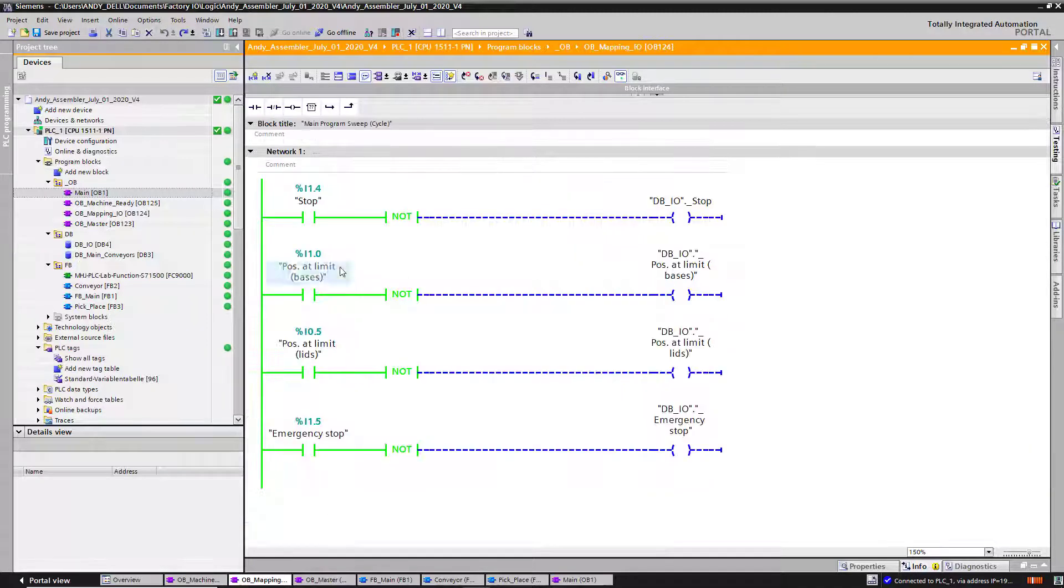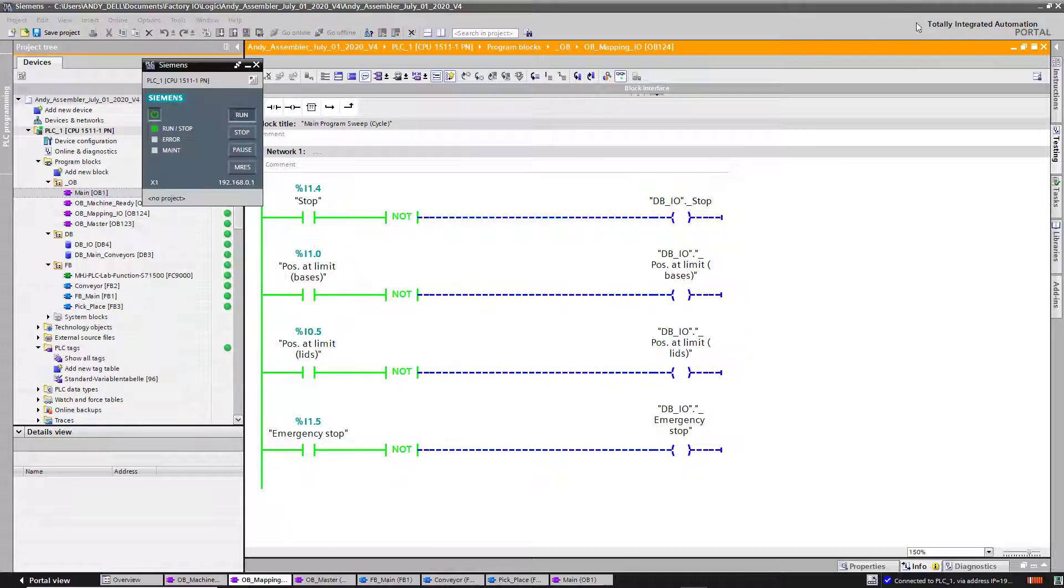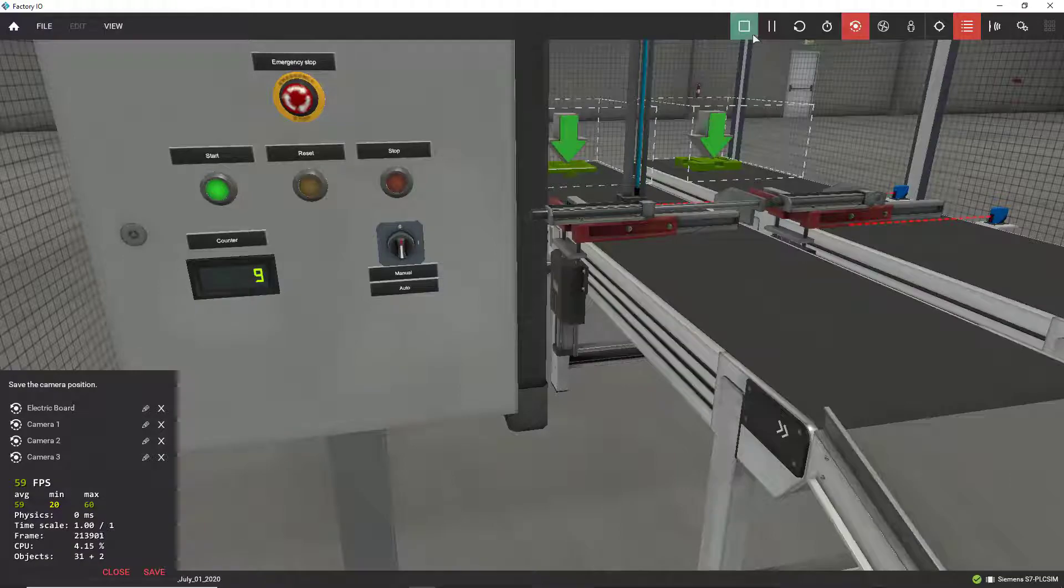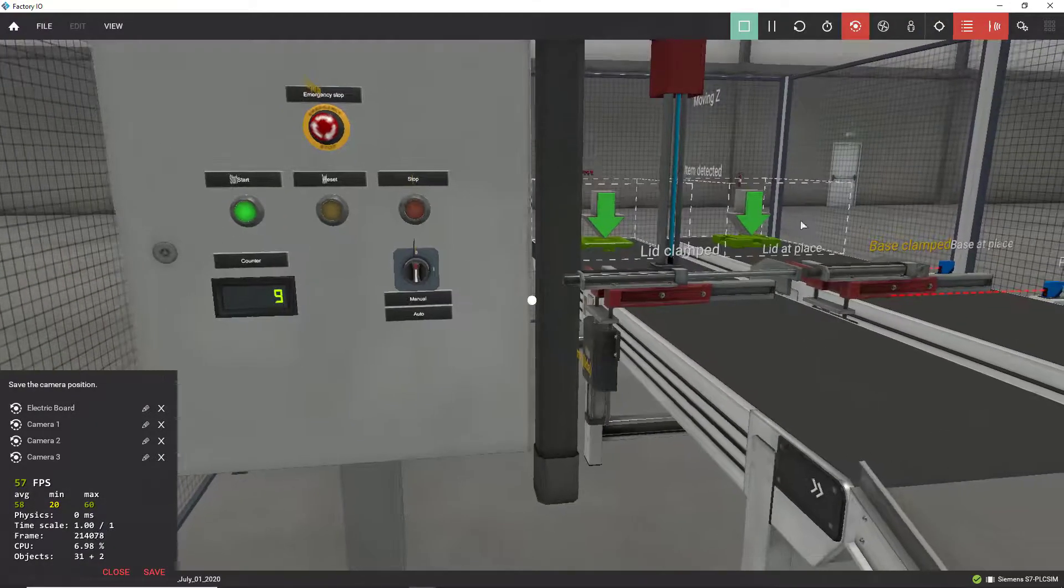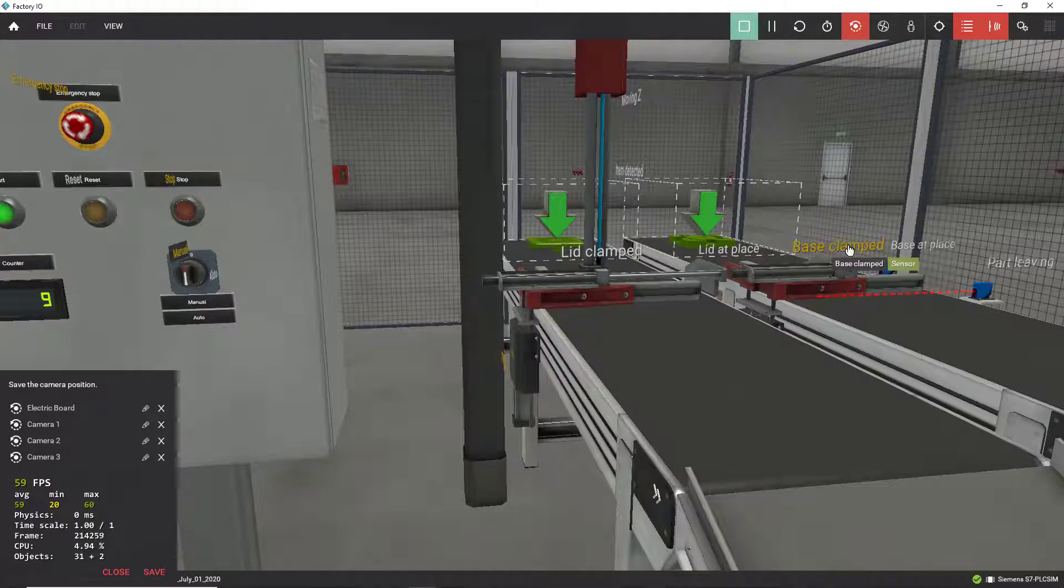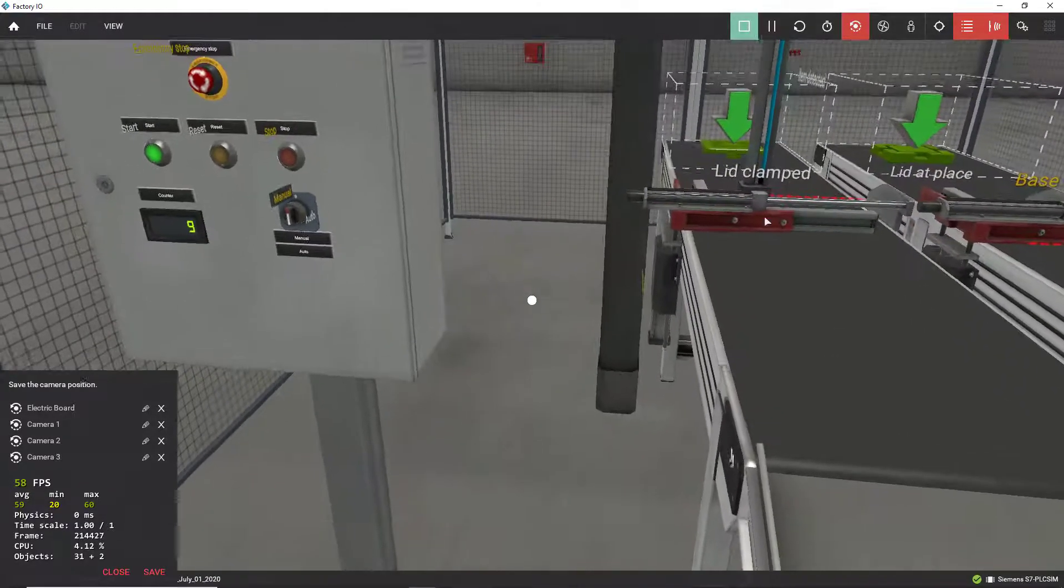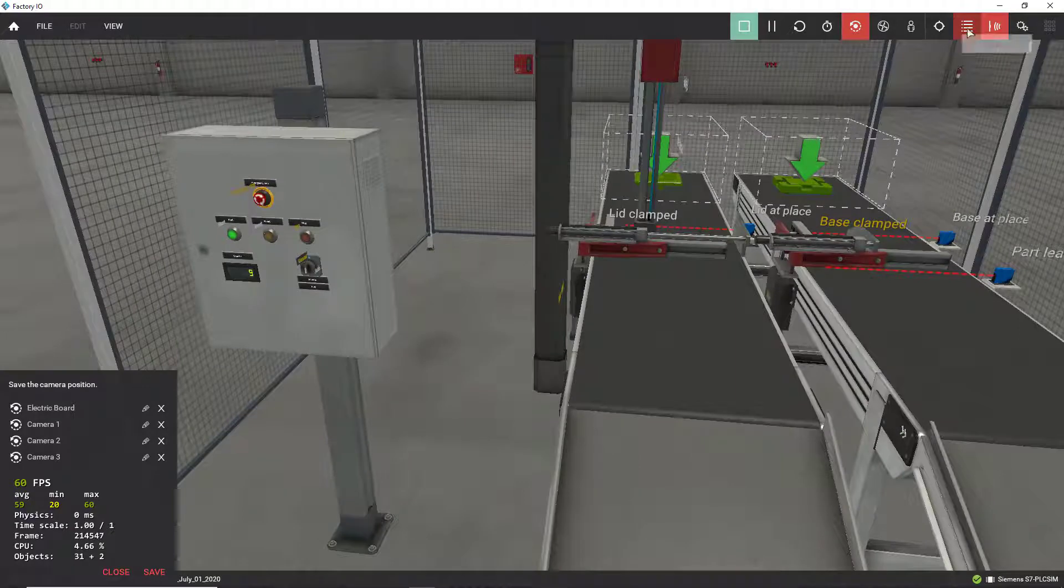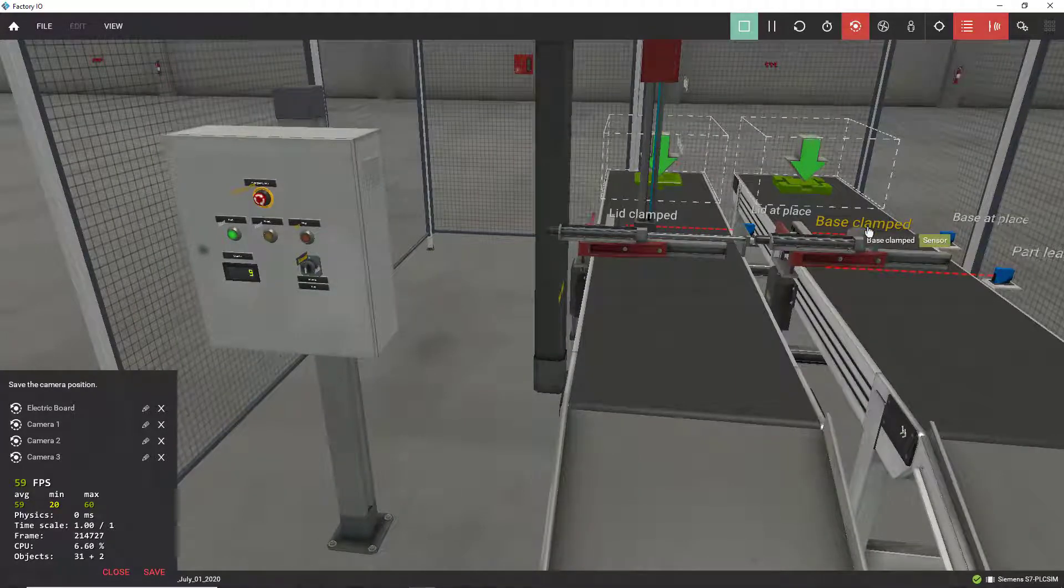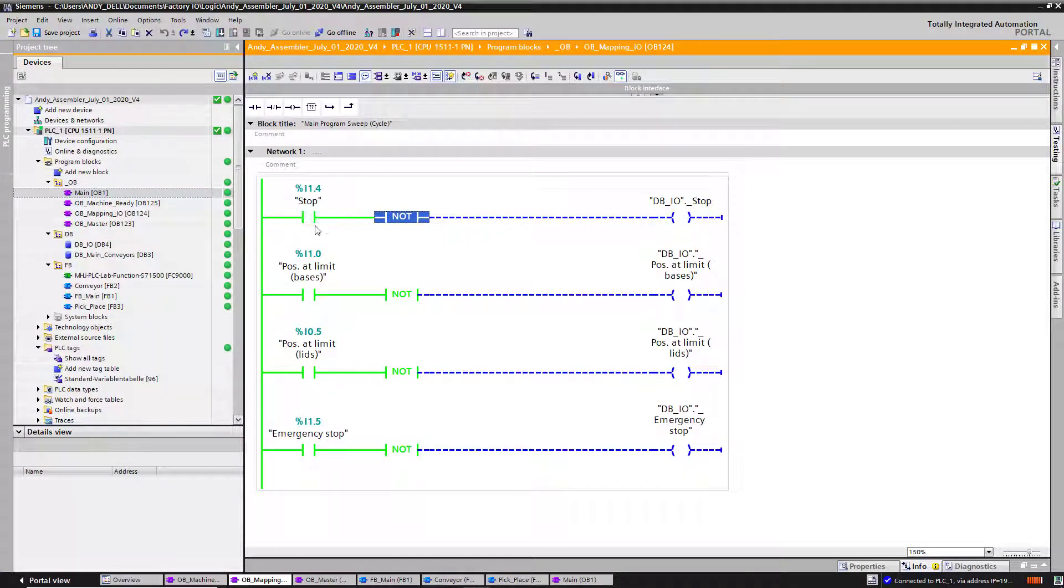I'm going to go ahead and do my mapping. This is what I do. I convert every sensor inside Factory IO. Everything you see yellow, this is a normally closed sensor. I'm getting those sensors and inverting them using this instruction. Invert the sensor from normally closed to normally open.